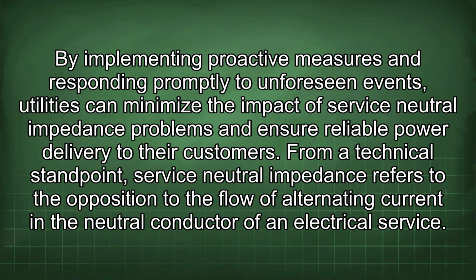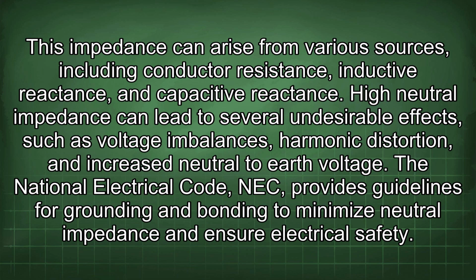From a technical standpoint, service-neutral impedance refers to the opposition to the flow of alternating current in the neutral conductor of an electrical service. This impedance can arise from various sources, including conductor resistance, inductive reactance, and capacitive reactance. High neutral impedance can lead to several undesirable effects such as voltage imbalances, harmonic distortion, and increased neutral-to-earth voltage. The National Electrical Code, NEC, provides guidelines for grounding and bonding to minimize neutral impedance and ensure electrical safety.